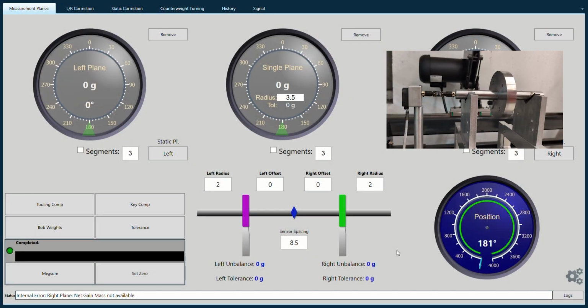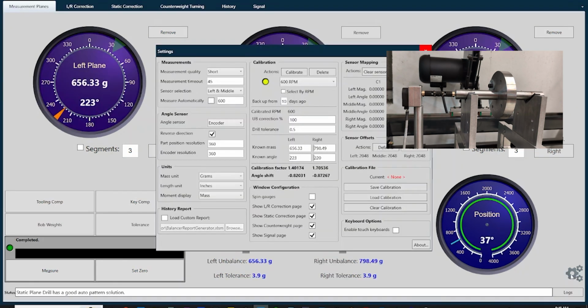With the software open, rotate the part by hand to verify that when it is spinning in the same direction that the motor will spin the part, the green arrows or the gauges on the screen are rotating clockwise. If it is spinning counterclockwise, then you'll need to go into the gears and check the box next to Reverse Direction. Note, if you are using a photo eye pickup instead of the encoder, you can ignore this check.